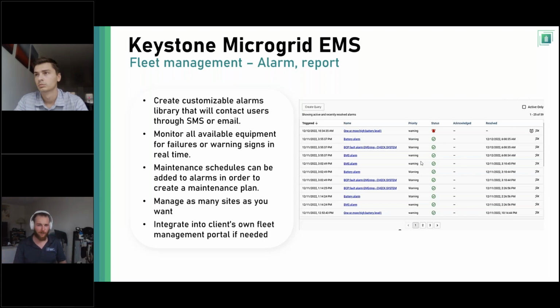You can set customizable alarms, not just for our equipment, but all the equipment that's feeding signals into our controller. So for example, a PV inverter, you'd have all the PV inverters sending Modbus commands to our controller, and it would say, okay, PV inverter 6 is down. We can send text messages, phone calls, emails to maintenance personnel, to on-site personnel to go out and check the inverters, make sure everything is okay.